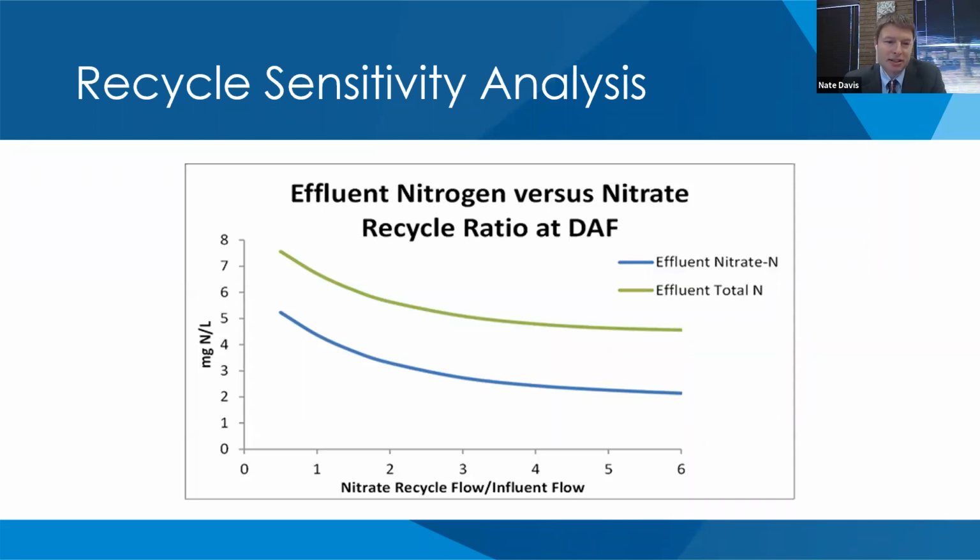on energy used to denitrify. In the event of low flows, you also want to keep an eye on these recycles, just to make sure that you're not bringing back too much. If you start bringing back too high of a ratio, you can risk bringing back high DO from that aerobic zone to your anoxic zone, and effectively you won't have an anoxic zone to denitrify then.